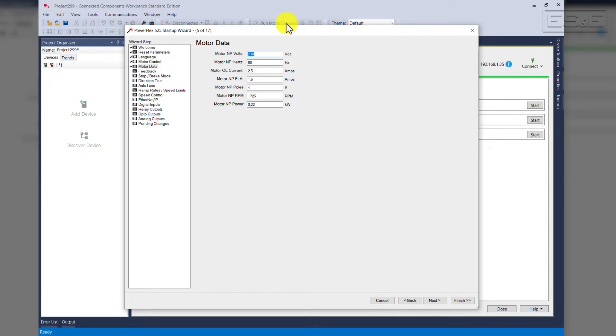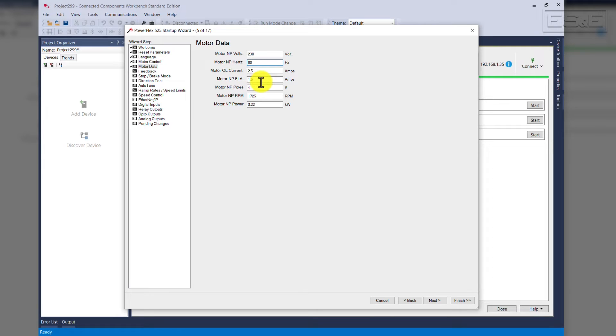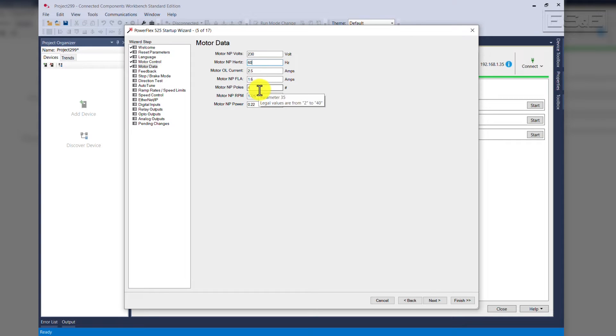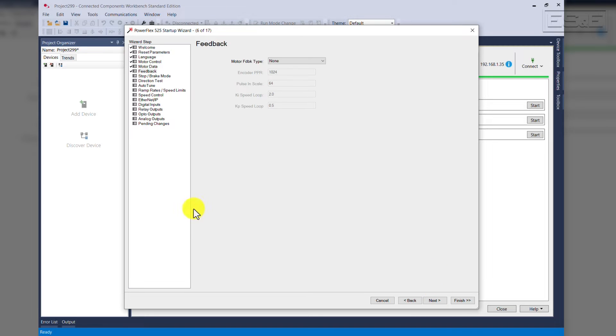Our nameplate data on the motor will come directly from the motor. We're at 230 volts, 60 hertz. Our motor overload current is at 2.5 amps. Our motor nameplate full load amps is 1.6 amps. The number of poles is 4, our RPM is 1725 RPM, and our motor nameplate power is 0.22 kilowatts. Click Next.